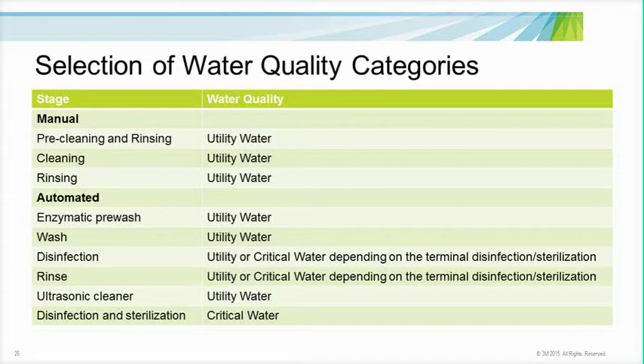This next slide shows the stages of reprocessing medical devices and the specific water quality that should be associated with this step. Utility water is used for all steps in manual cleaning and the first steps of automated cleaning. The disinfection should use critical water. This may depend on if the device will be terminally sterilized or just disinfected.